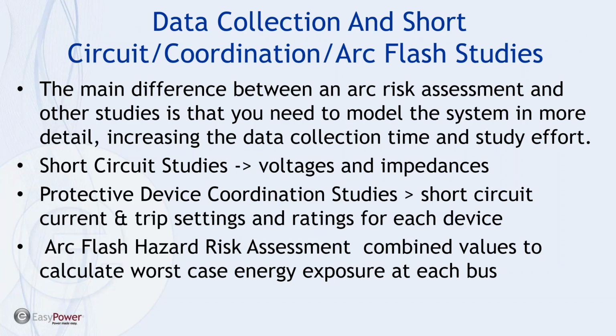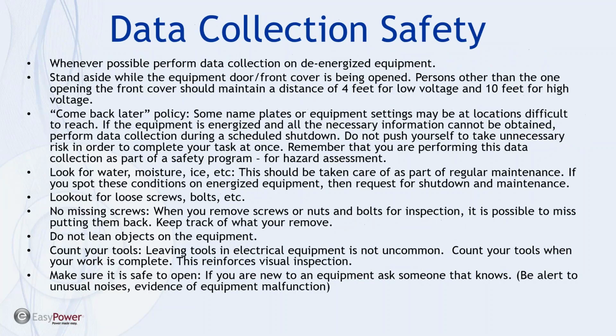As you get into understanding the implications, there are reasons to do a short circuit study first and protective device coordination second, before you complete the arc flash risk assessment, because they're all interacting parameters that you're collecting data on and analyzing. Whenever possible, you want to make sure you're doing data collection on de-energized equipment. And this may mean that you come back later rather than just force ahead during operations. That's what I mean by having a big picture plan of attack.